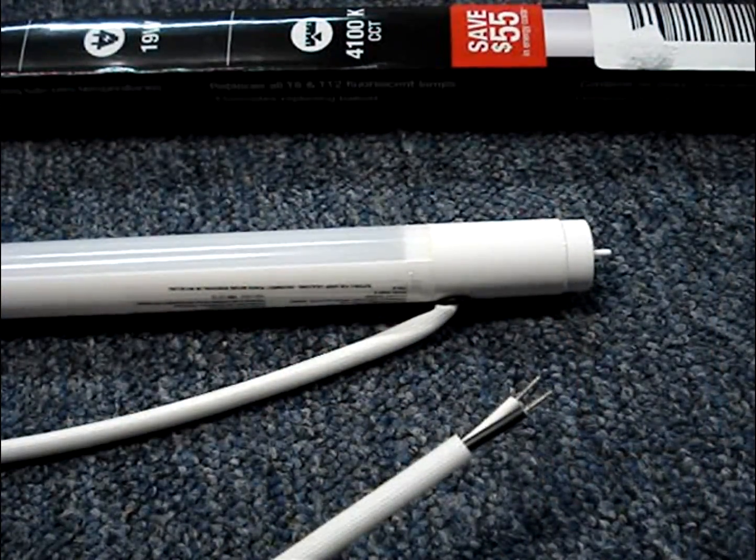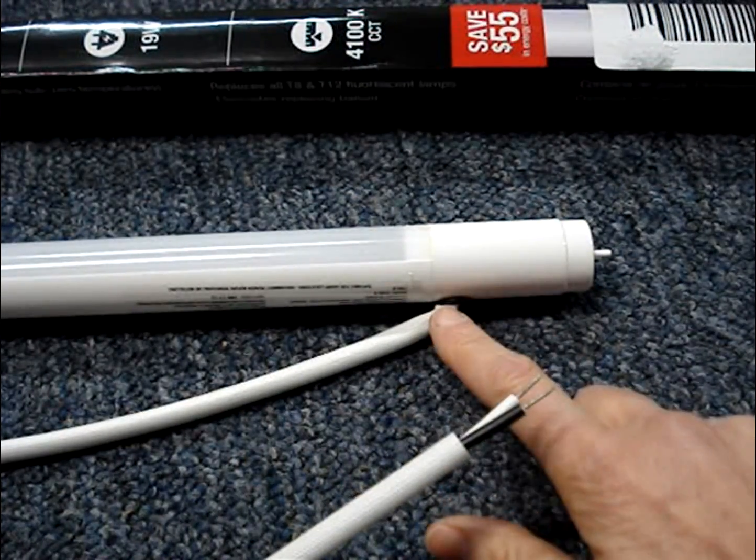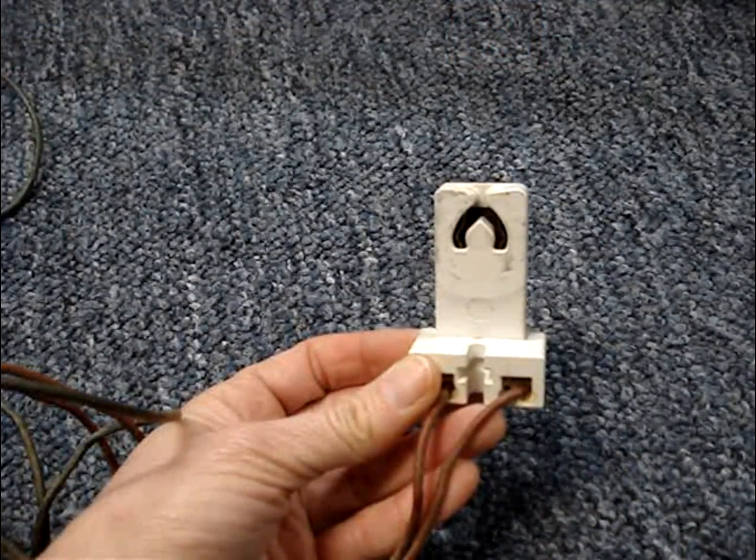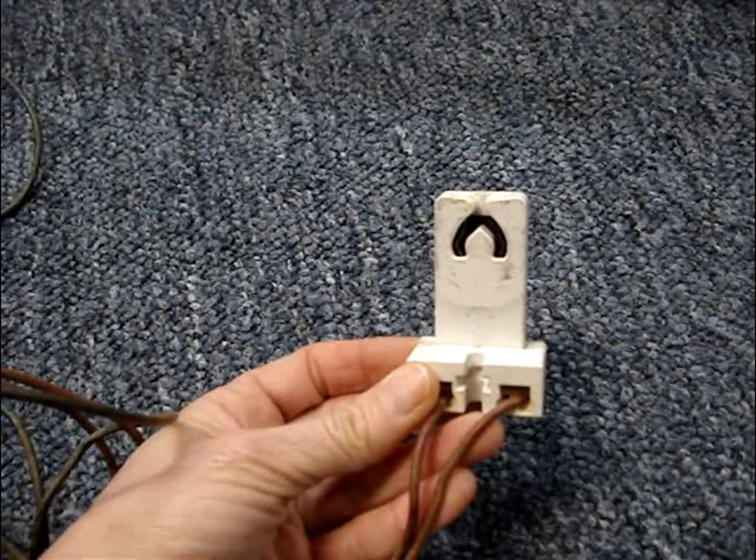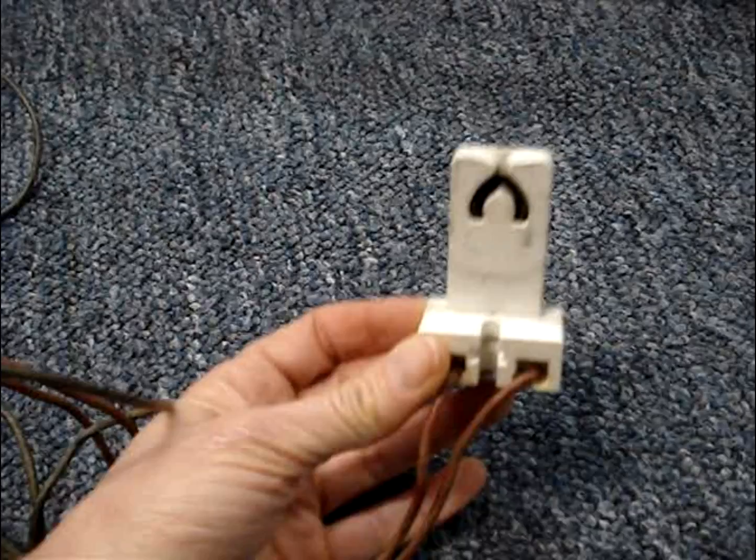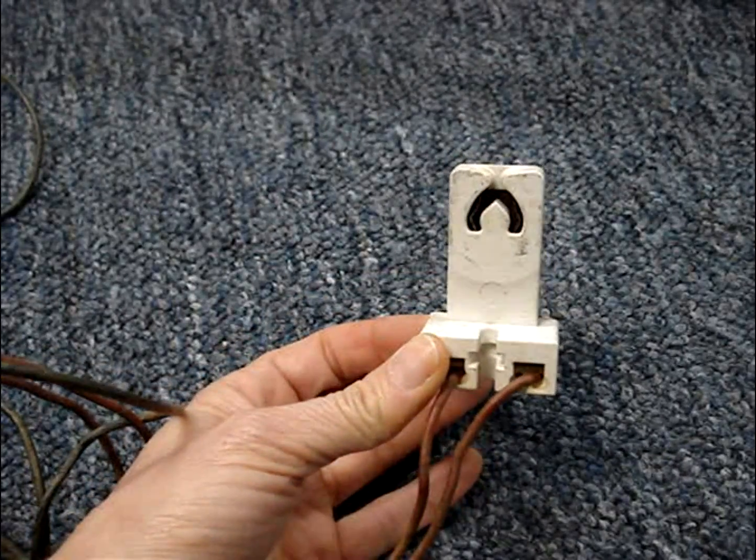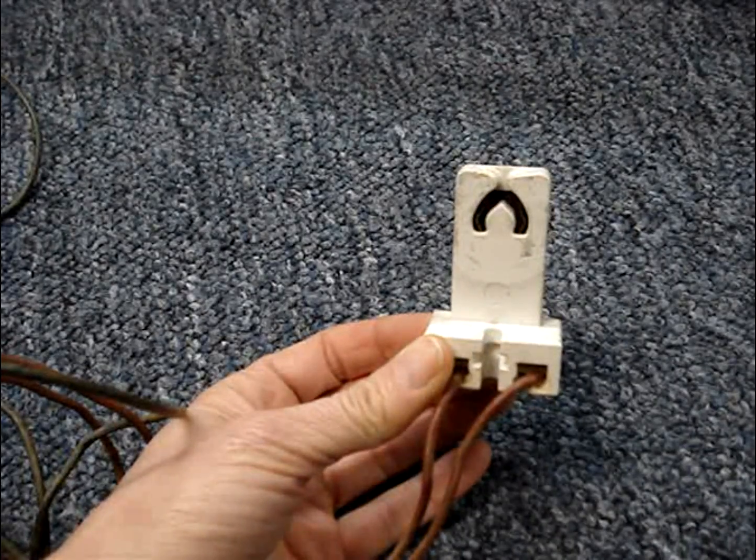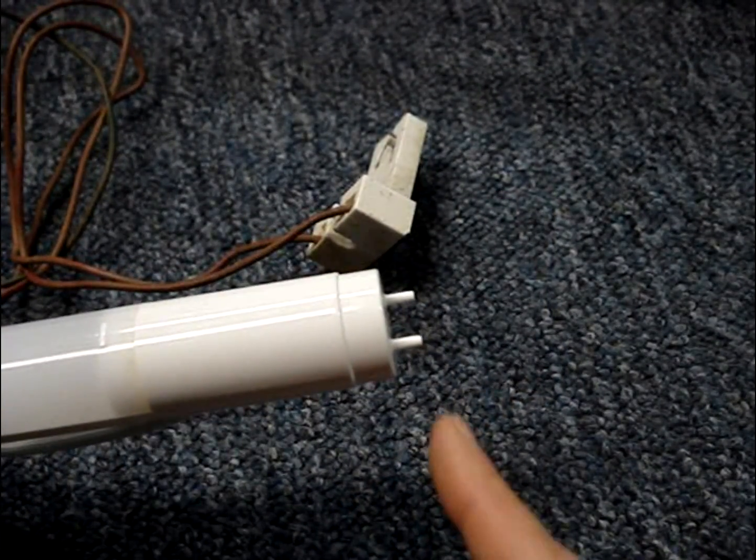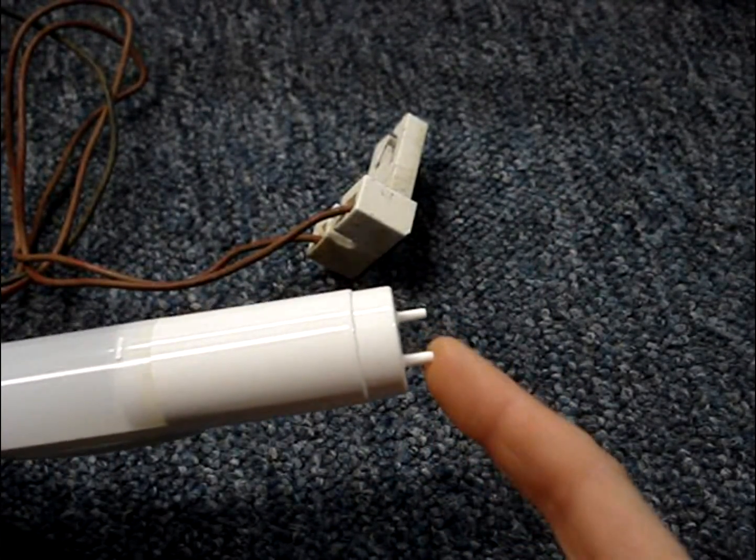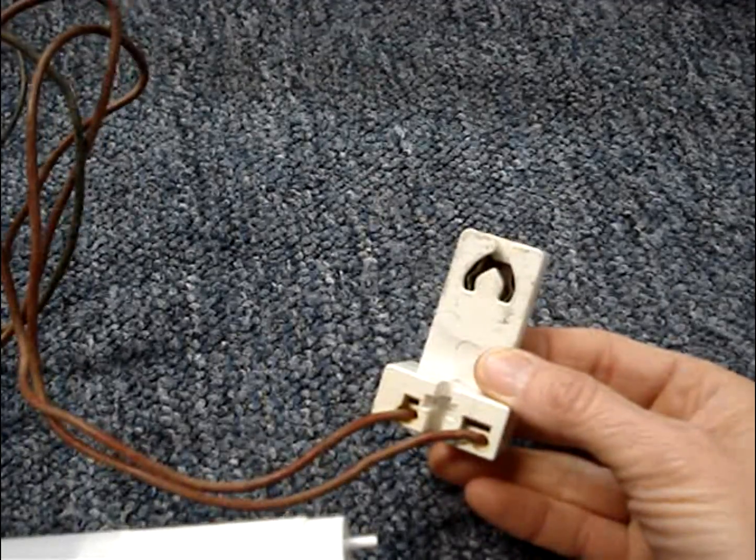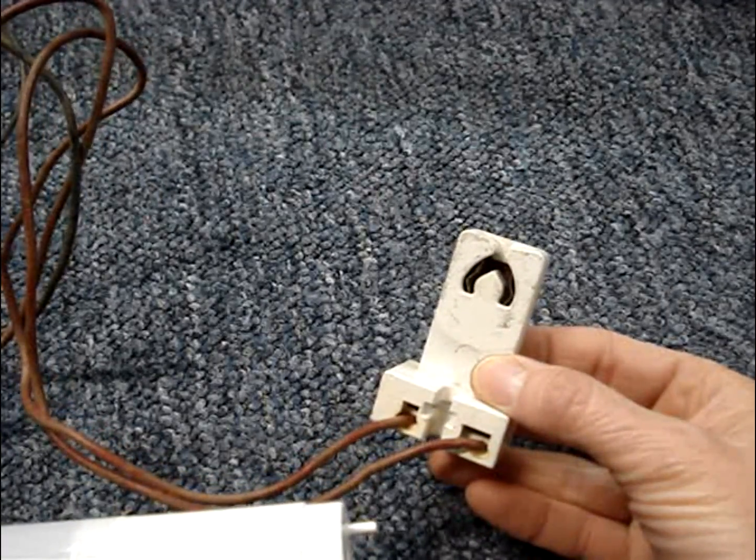You simply need to connect the hot and neutral that's connected directly to the bulb into your house circuit. You don't have to figure out your wiring configuration or rewire any tombstones or possibly replace the tombstones. The ends of the tubes are plastic and don't have any power connections. The tombstones simply become holders for the new LED tubes.